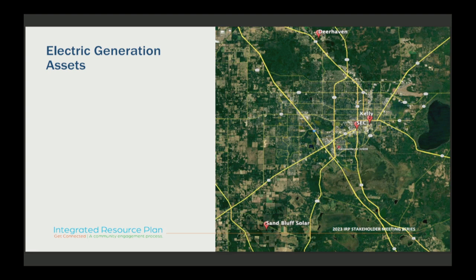And I'd just like to point out, a lot of people have this idea that there are huge transmission losses, given the voltages you guys are running. I don't know if you want to speak to the losses specifically, but you can move electricity around. Yeah, typically the reason why we use transmission is to lower the amount of losses that we have. Typically on our system it is less than 2% losses that we calculate or at least factor into our delivery service. So there are some, but they are small.